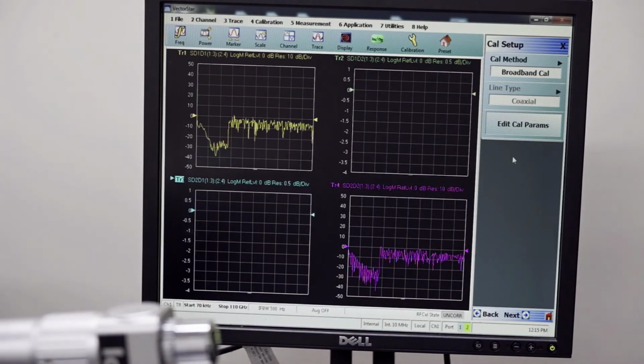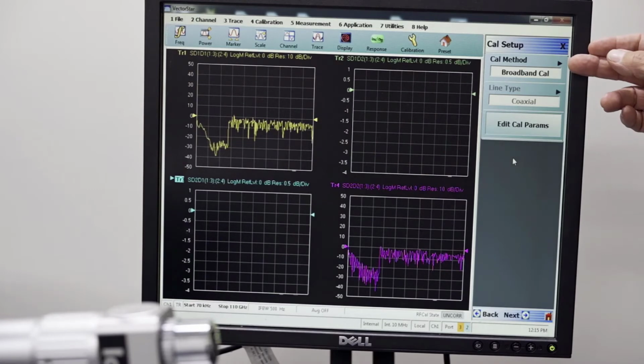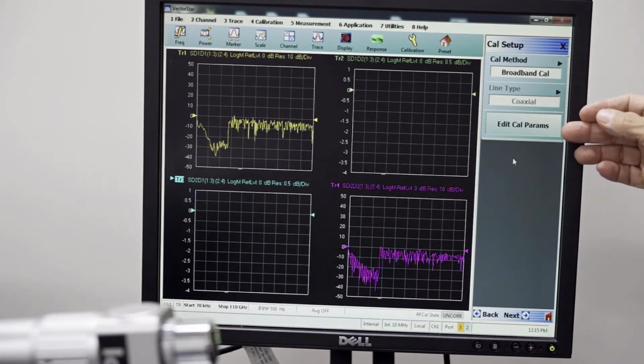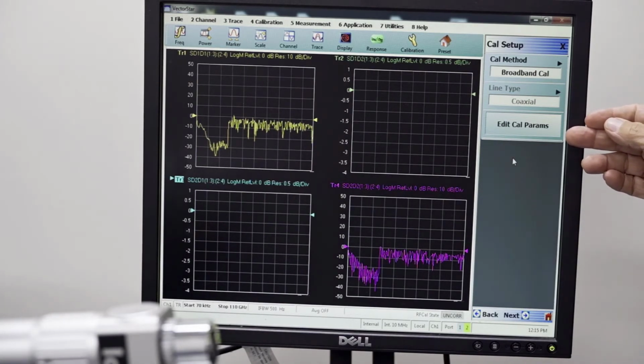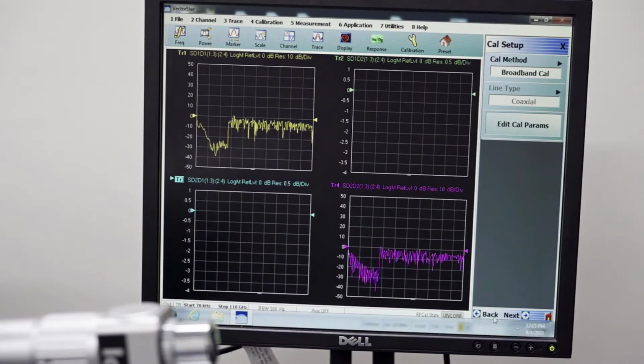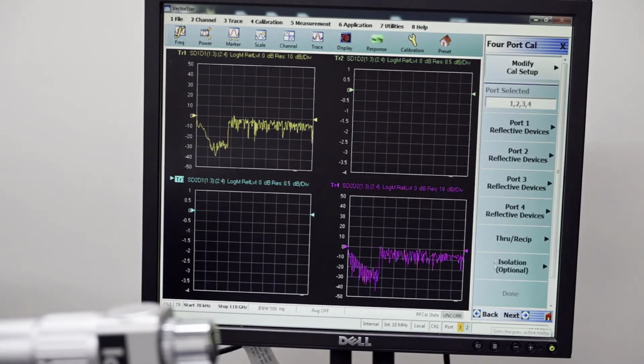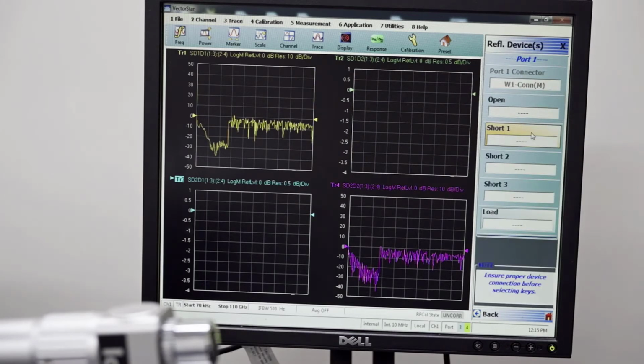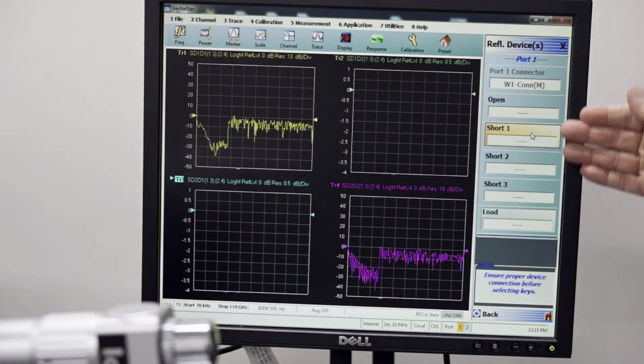So we click OK, and that's where we're finished with our setup. We've defined the cal method, and then we've edited the calibration parameters to designate what standards we're going to be using. And so now we can start our calibration by selecting port 1 and then connecting our coaxial standards to the test port.